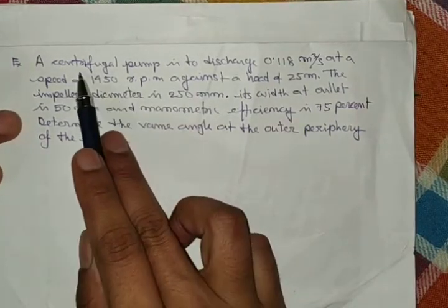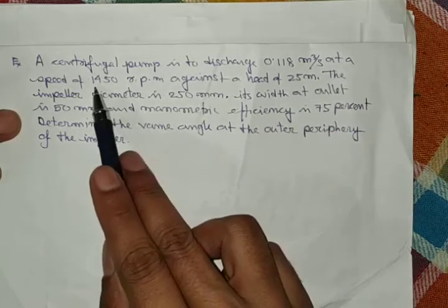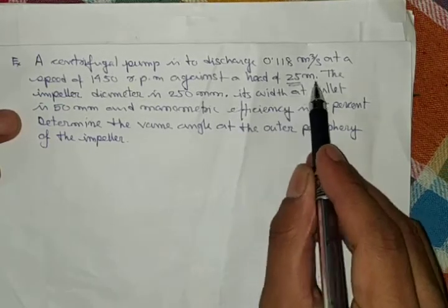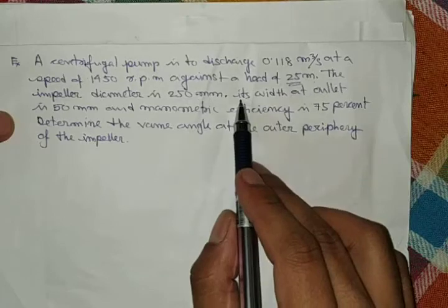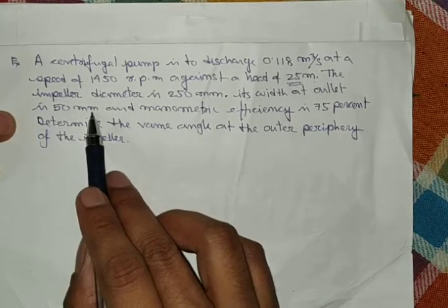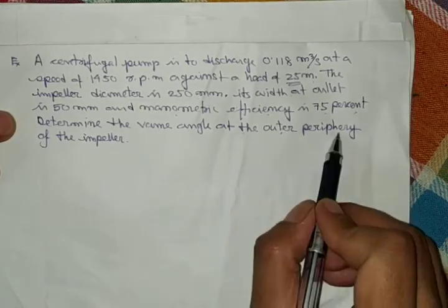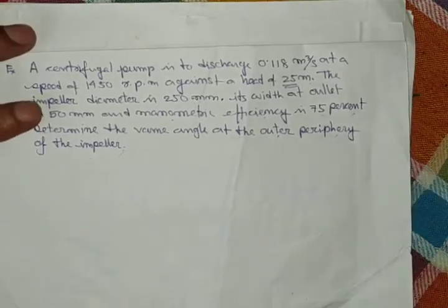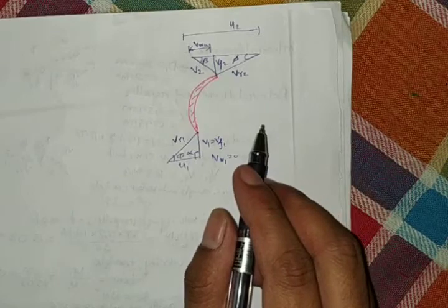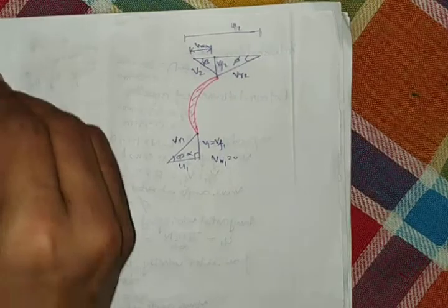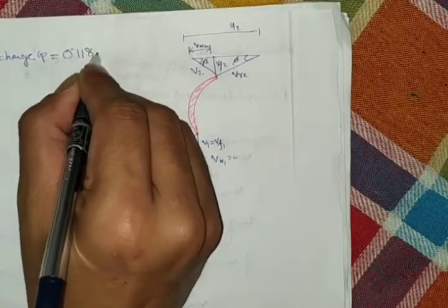Now let's try another problem. A centrifugal pump is to discharge 0.118 m³/s at a speed of 1450 rpm against a head of 25 m. The impeller diameter is 250 mm, width at the outlet is 50 mm, and manometric efficiency is 75%. Determine the vane angle at the outer periphery of the impeller.